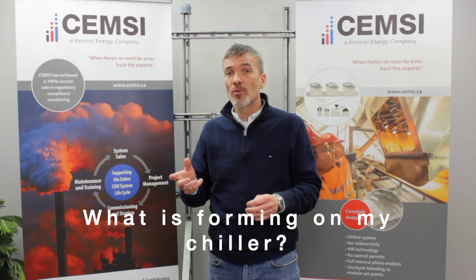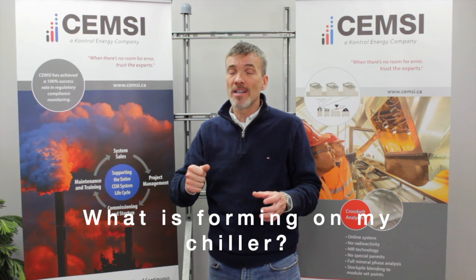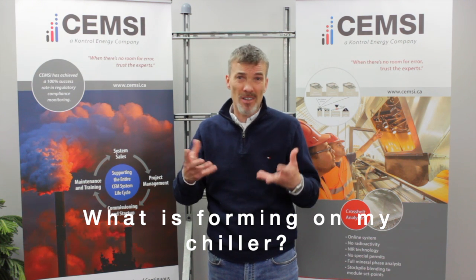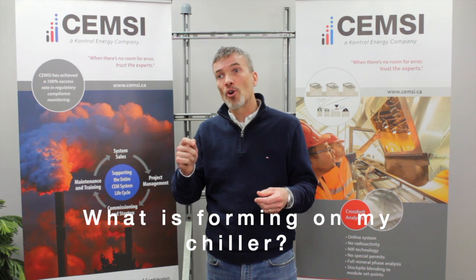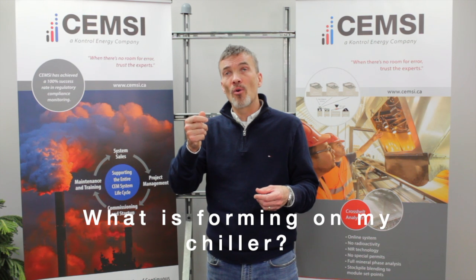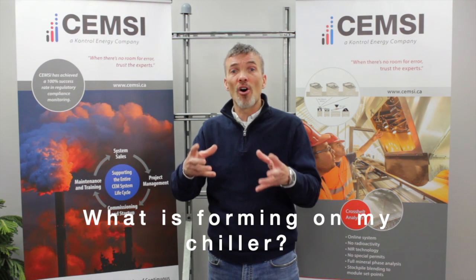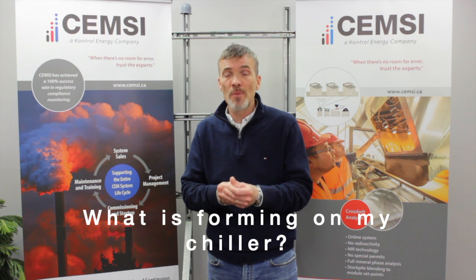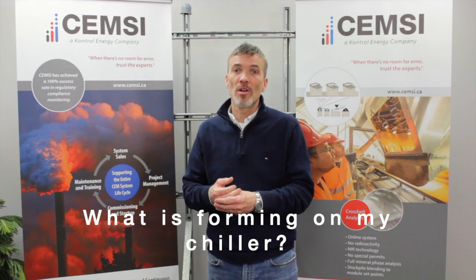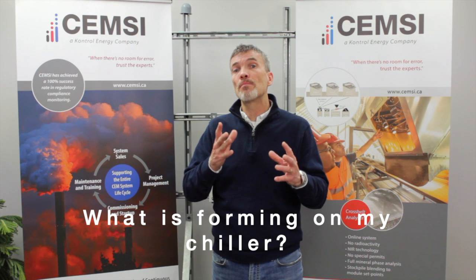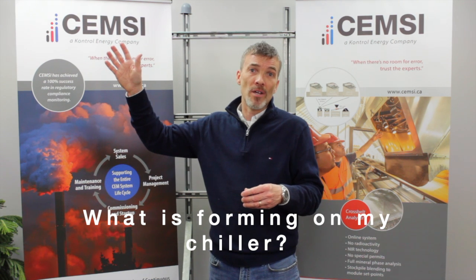The only time you have to worry is when you squirt hot water on it and it doesn't dissolve. That's when you can start looking at whether it's a hydrocarbon-based product, which is usually black because it's a tar, a petrochemical-based product, or if it's granular or gritty and you retain it, it doesn't break down, it stays there, or it just breaks down and doesn't dissolve. You can still see the grit in the bottom of the glassware. Then you could actually be dealing with an actual piece of particulate. If you're forming particulate, then it means that your probe's not doing the right job of filtering.